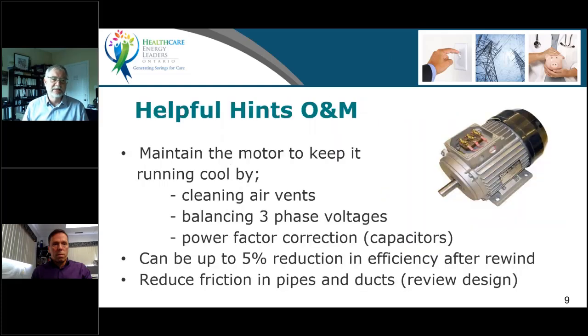So on motors, some helpful hints are maintaining the motor in good running condition and balancing the 3 phases. If you've got voltages to a motor that are inherently imbalanced, that will create heat in the motor as well. Certainly, we can reduce the line current to a motor by using power factor correction, things like we talked about in the previous section. But watch those rewinds, and then ultimately look at what's going on downstream, and that's where we're going next.